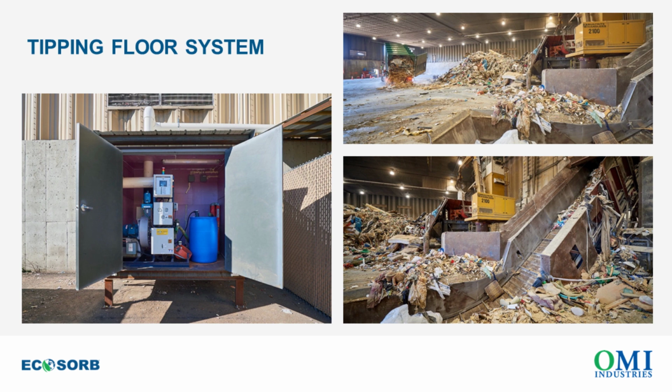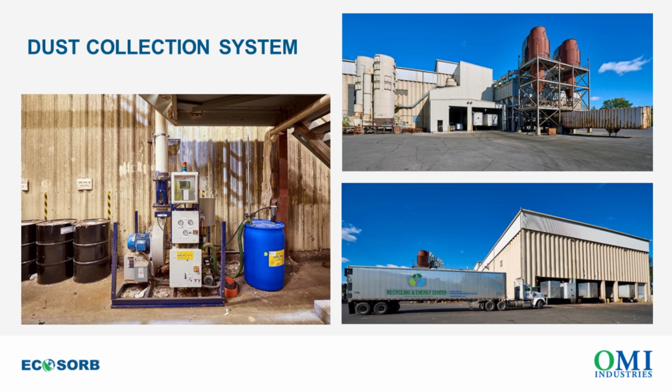This next slide is just an example of the system that we have over the tipping floor. So it's a 60,000 square foot tipping floor where we're dumping garbage. And you'll see PVC piping up on the top right and the bottom left, and that's actually pushing to those 7 active roof ventilation fans. On the left is the OMI system. It is located outside, so there has been a doghouse built around it, both to protect it and also to control the temperature. So that's the first system for the 30% of the odors.